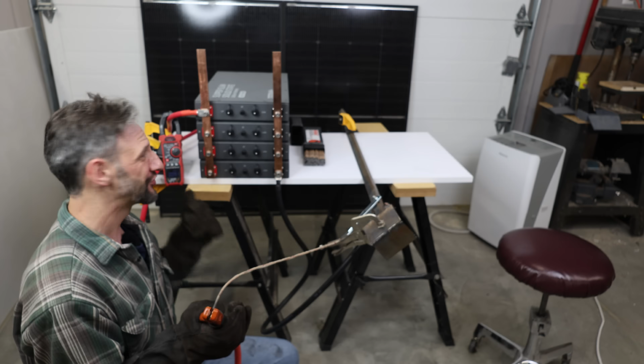So the problem is we can't weld at that low of a voltage. If I want to weld, I'm going to have to raise the voltage. I can break this stack into two. Clearly the current isn't our biggest problem, it's the voltage, so I'm not going to need these huge bus bars. I think I can put two in parallel and then those two in series, and we can get 24 volts at 400 amps.